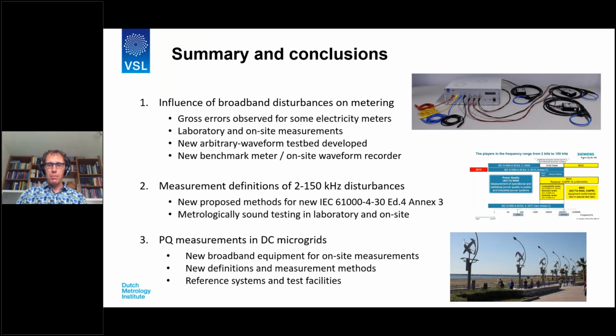The second topic was on the measurement methods of supraharmonics in support of IEC SC 77A Working Group 9 to improve the standard 61000-4-30. And 2 new methods have been proposed that are currently being tested using laboratory measurements on specific electronic appliances, among others an EV charging converter, and also on-site measurements. The third topic was power quality disturbances in DC grids, which are currently not defined yet. The idea is to develop DC broadband equipment and to perform on-site measurements to see what is actually present in DC grids, and then to derive new power quality definitions and measurement methods from these. And to guarantee traceability, reference systems and DC electricity meter test facilities will be developed.